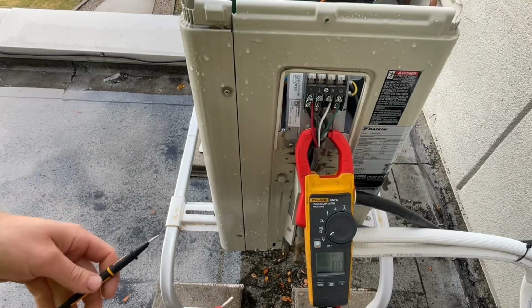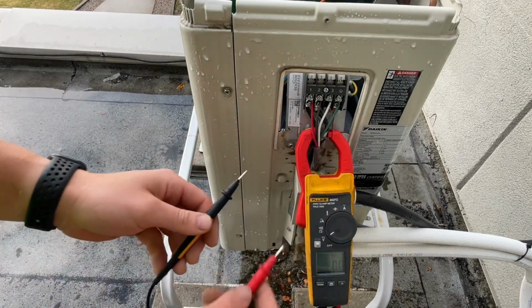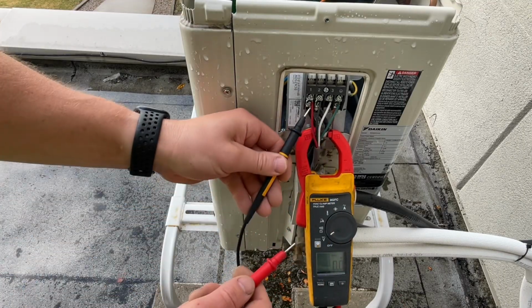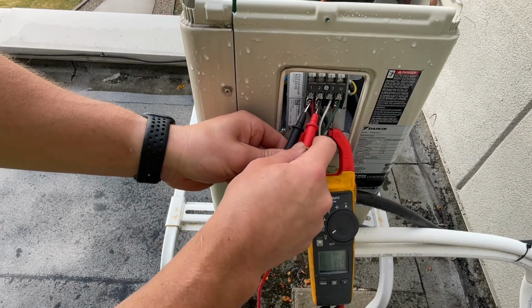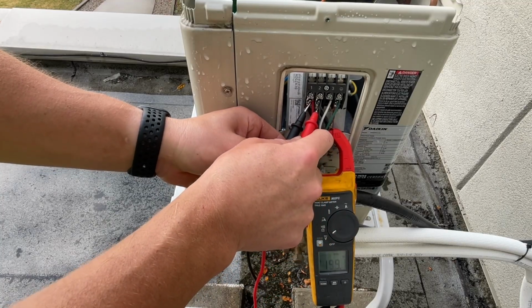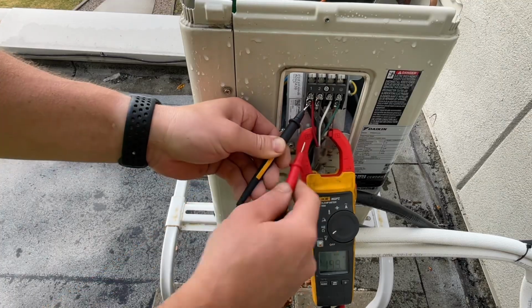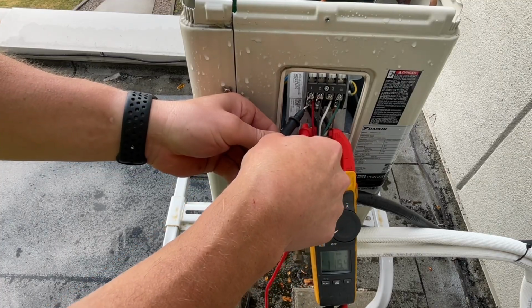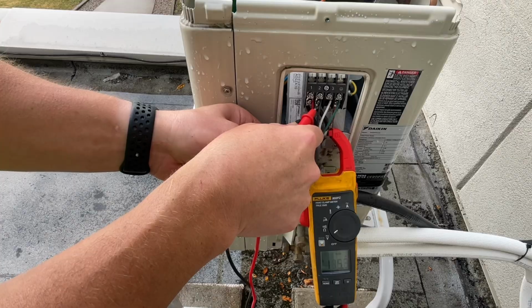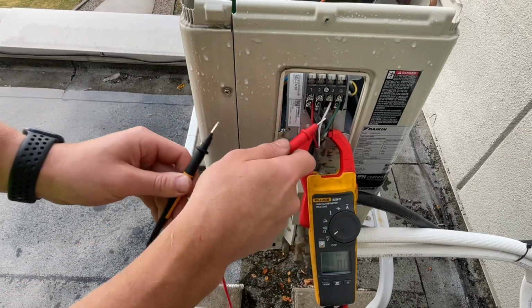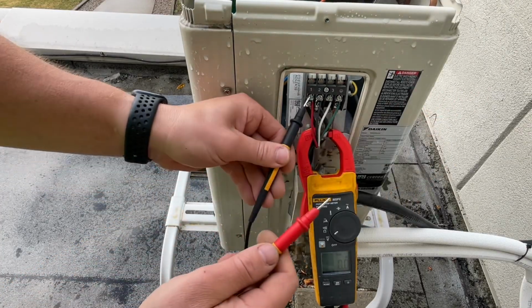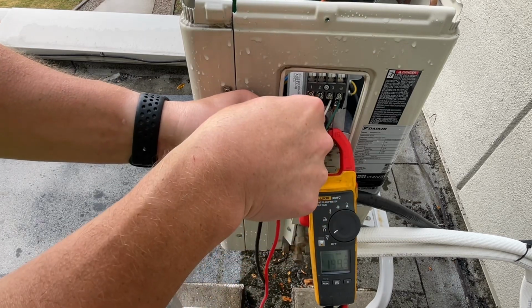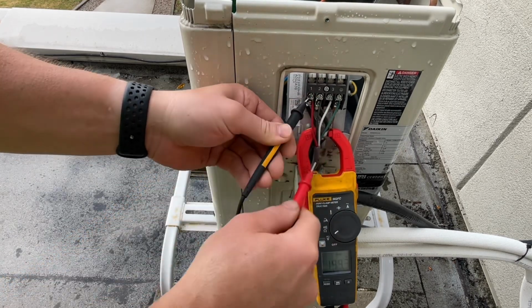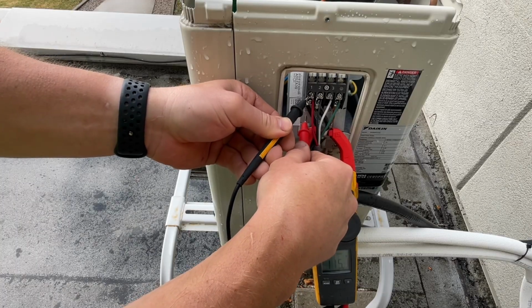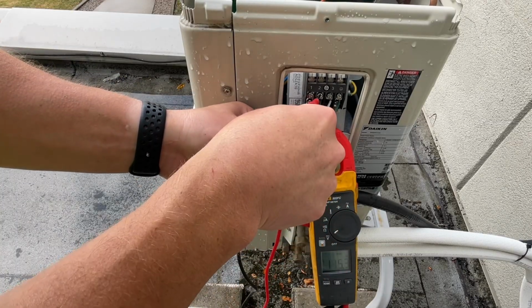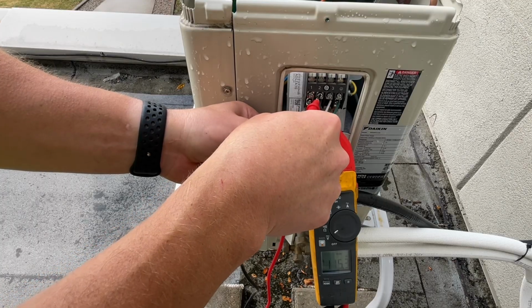All right, we'll do some basic first checks here. We'll check our inlet power here, which is our terminals on the bottom here. So we're looking for 200 volts, 208. We got 199. We know we have power coming in. No problems there. We'll check to ground per leg, 115, which is good. And our other leg, 115, is good. 1 and 2 is our power to our indoor unit. We'll verify that. We shouldn't have any issues there. 199, perfect. 1 to ground, 115. 2 to ground, 115. So our power's good.